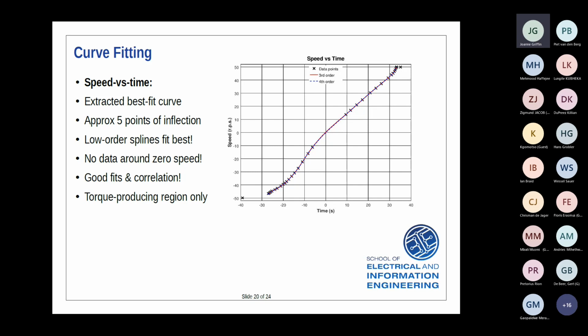If you have a single cage rotor, you've got one circuit, so probably a third order function. If you have a double cage machine, you have two parallel rotor circuits. That brings in another order of complexity, and a fourth order curve would fit that data.